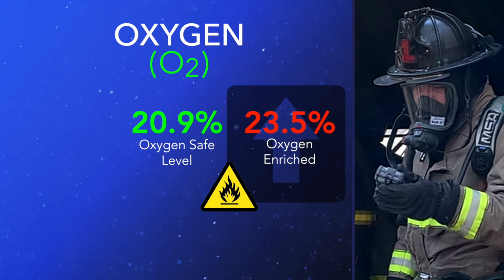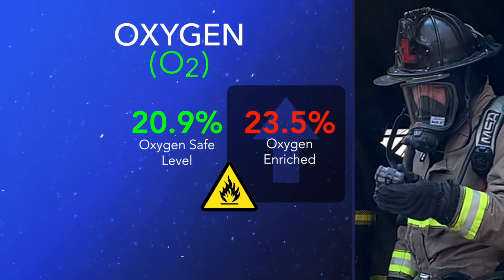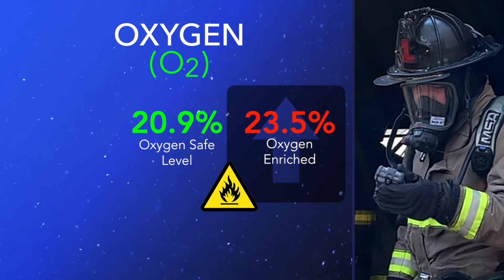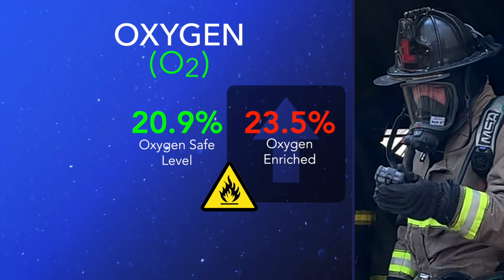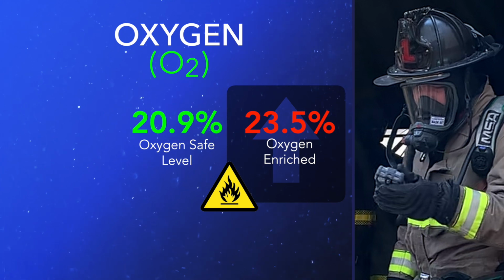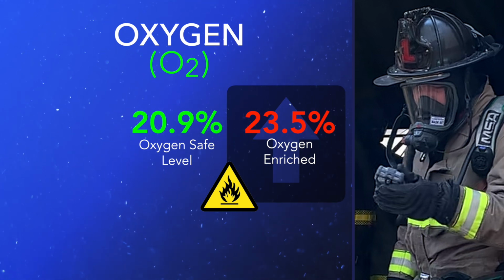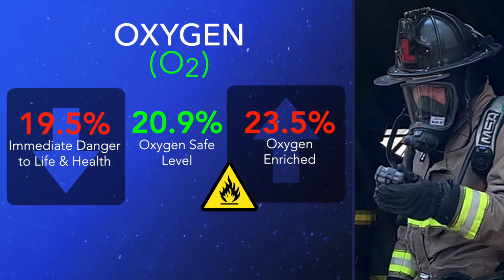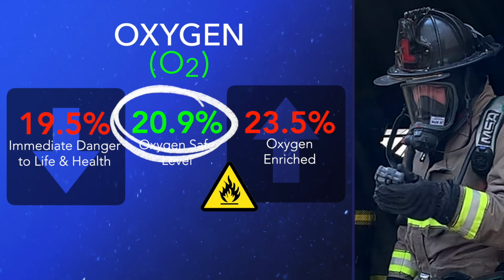Sources of oxygen enrichment are most common in medical, industrial, or welding businesses that use pressurized oxygen, cryogenic gases, liquid oxygen, oxygen vents, and other oxygen sources that can increase oxygen levels. Oxygen levels at 19.5% or lower are considered an immediate danger to life and health. The acceptable oxygen levels in an ambient environment are between 19.5% on the low side and 23.5% on the high side. When we think of the oxygen level on a gas detector, think of the number 20.9%. If this moves in either direction, start thinking about what might be displacing or increasing the oxygen level.